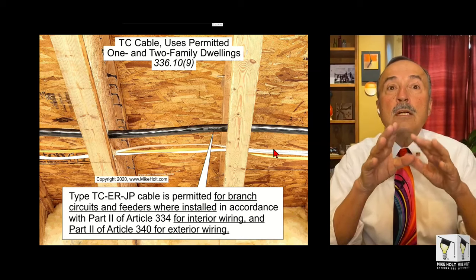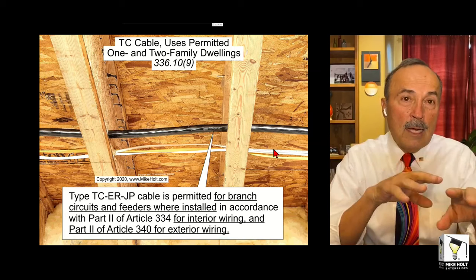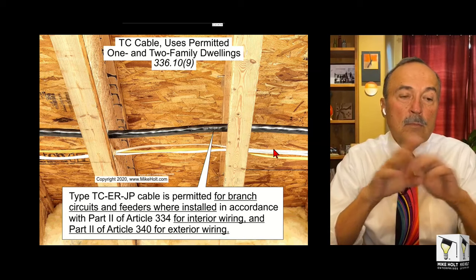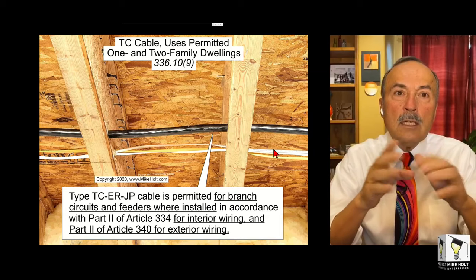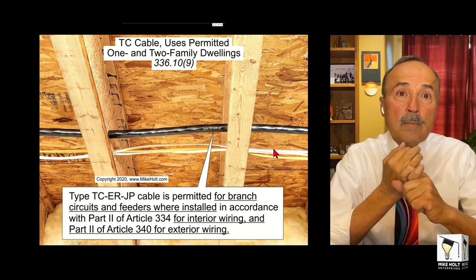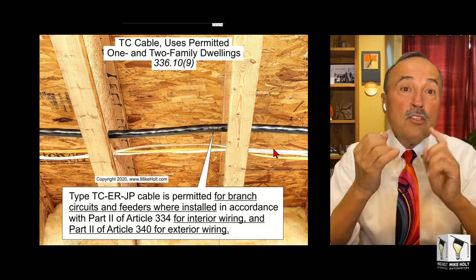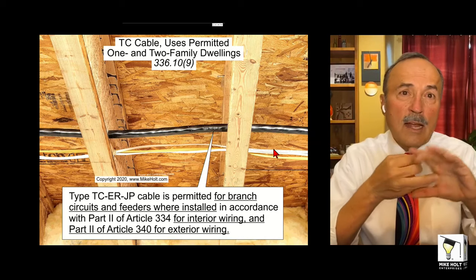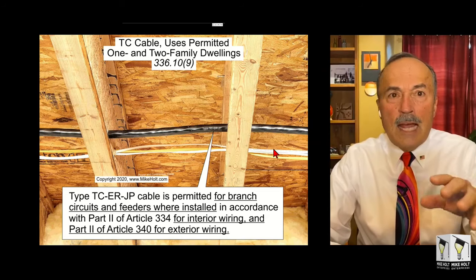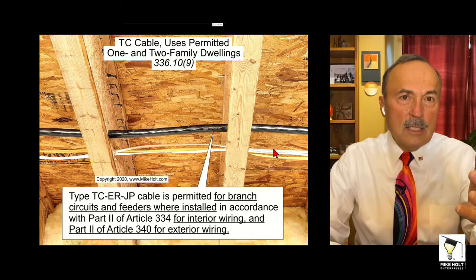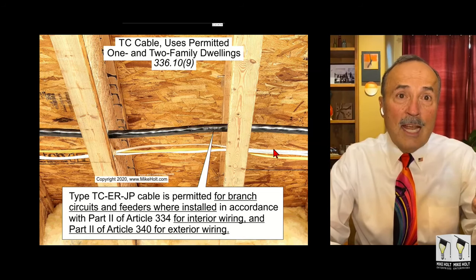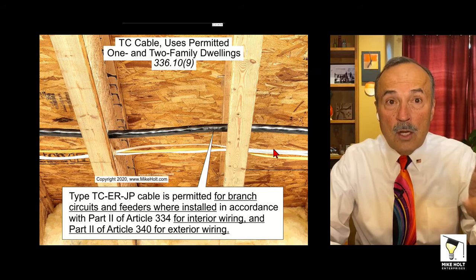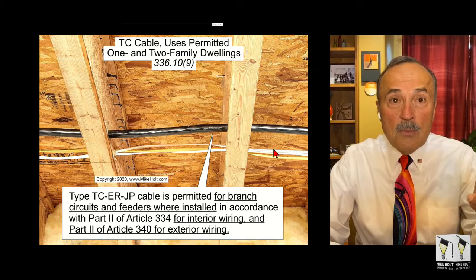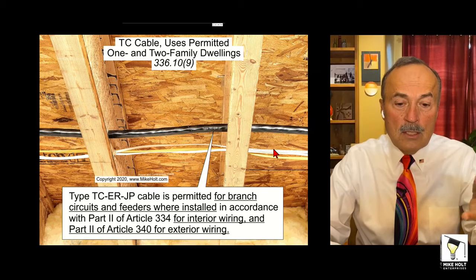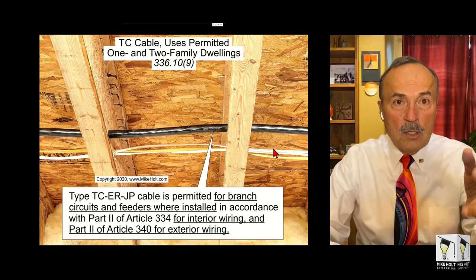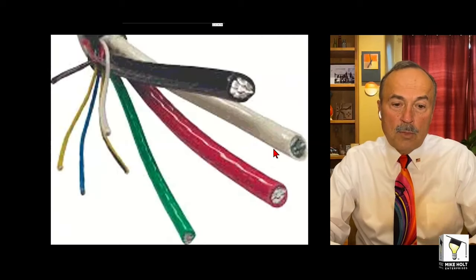So if you're going to use this tray cable that Generac supplies, or that you can buy as a dealer, then you can put it inside of a building. And you can put it outside of a building. And it can be direct buried. It doesn't have to be in a raceway. It doesn't have to be in a cable tray. So the question that was asked was probably like, they wanted to use this cable, and the inspector says you can't use that cable. And it was probably the 2014 code, which said you could not use it. But the 2017 code modified it, and you can see that the 2017 code modified it. And the 2020 code just kind of improved it a little bit.